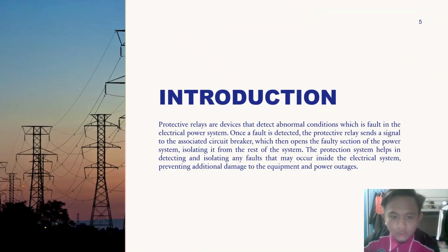Okay, now we are going to the introduction. First of all, protective relays are a device that detects the abnormal condition, which is fault, in our electrical power system. Once the fault is detected, this protective relay will send a signal to the circuit breaker. Then the circuit breaker will open the faulty section for our electrical power system, isolating it from the rest of the system. This protection system is used to avoid additional damage to the equipment and power outages.